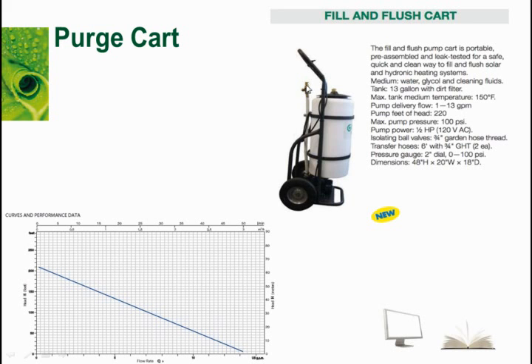pressure gauge up here. It's a glycerin-filled, stainless steel case, 100 PSI gauge. This thing will pump up around 100 PSI. And so what that'll do for you is once you pump your fluid into your system, you can shut the valve off here, and now your gauge becomes a gauge that you can watch and make sure that you don't lose pressure, that you don't have a leak somewhere in your system. So it's kind of multi-purpose. Not only is it a purge cart to put the fluid in, but it's also a test rig so you can make sure that you don't have any leaks up on your collectors out in your system.